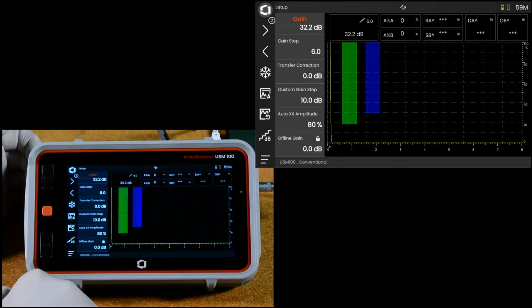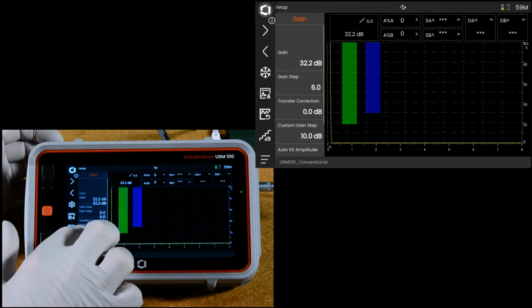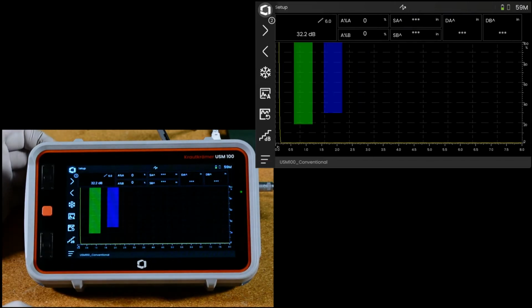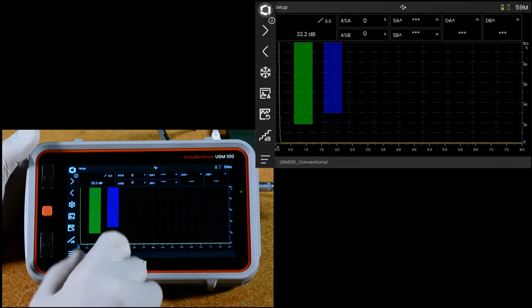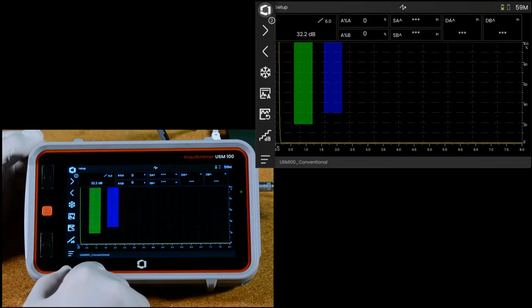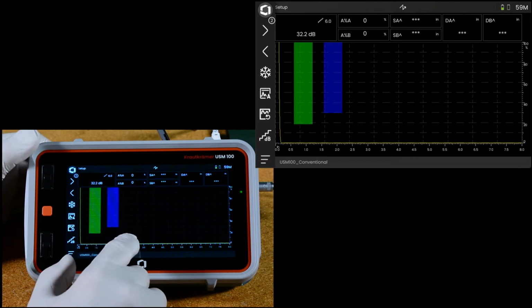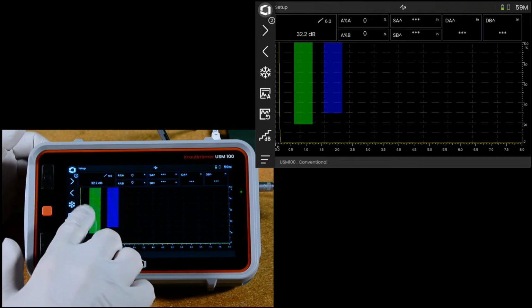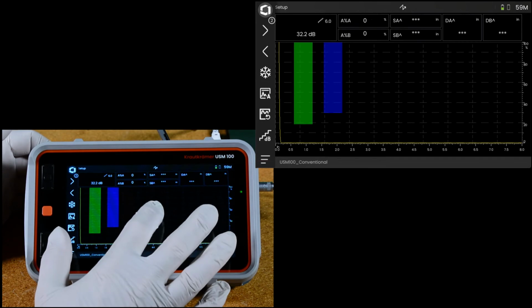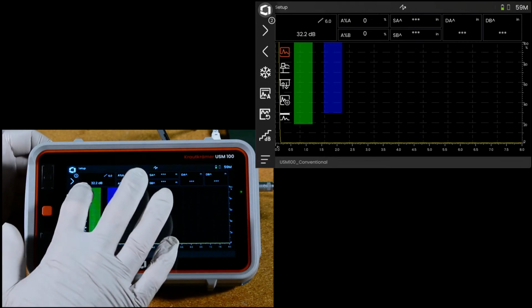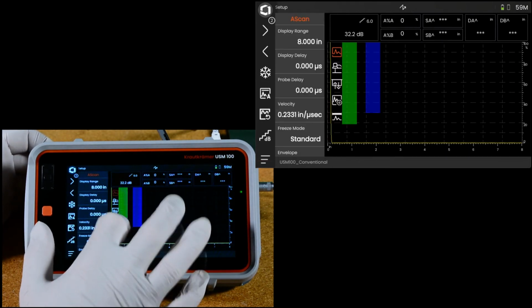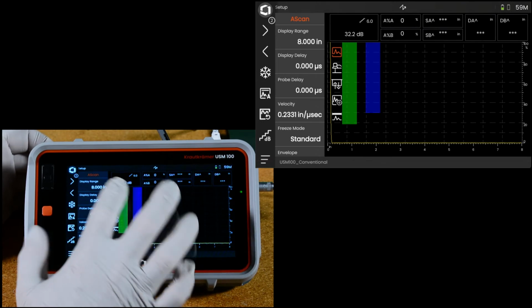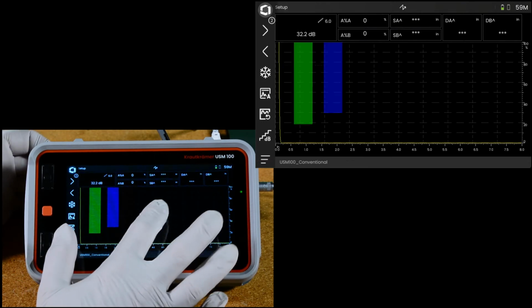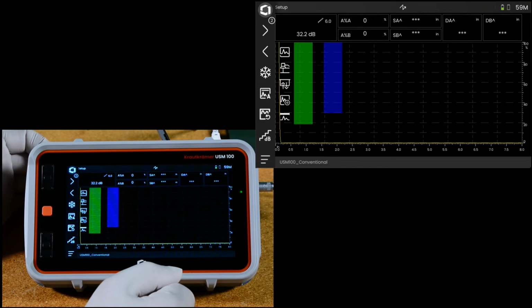Transfer correction, other gain pertinent items are on this menu. Close that by just hitting the gain control another time. Now, various data views also have menus that are specific to them. In the case of the A-scan, we access the A-scan menus by tapping the A-scan, and we see menu buttons appear on the left edge of the A-scan. If I close that, tap the A-scan, the menu buttons appear.